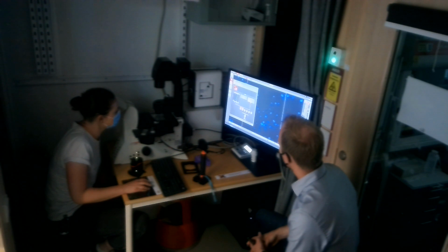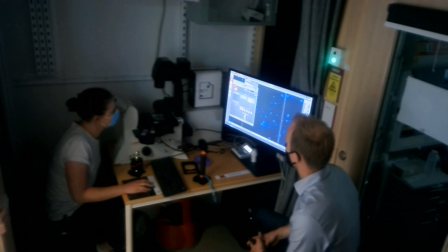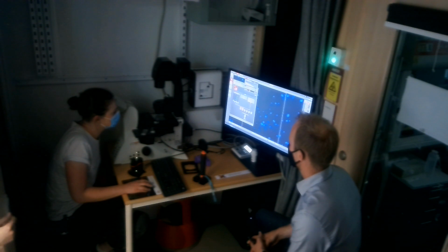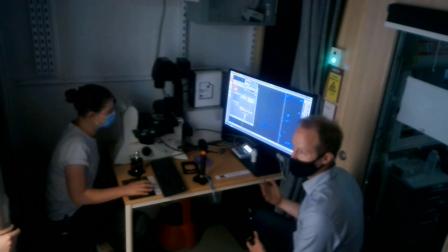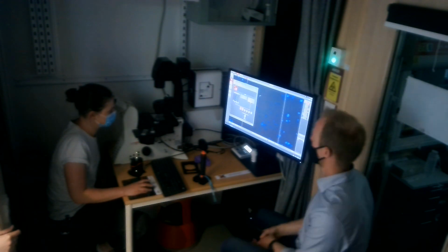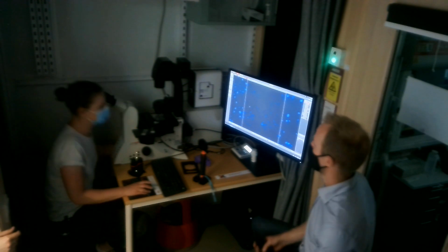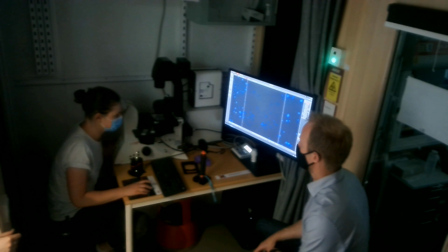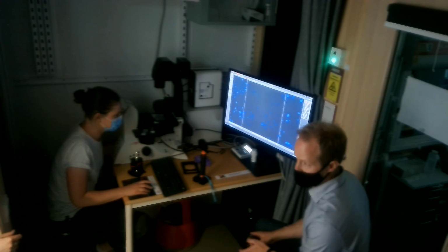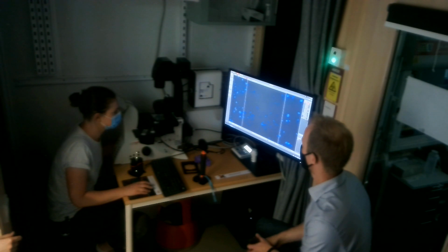So here it's also already in 4. Yeah, so these are very bright. You're on 4 there, you have a very short exposure, 20 milliseconds, you can go down to 10. I would probably not go down below 10 normally, because once you start going to very short exposure time, you're also introducing other things that can decrease the quality. So I would try to stay between 10 and 20 at the low end, and then decrease the power of the LED.